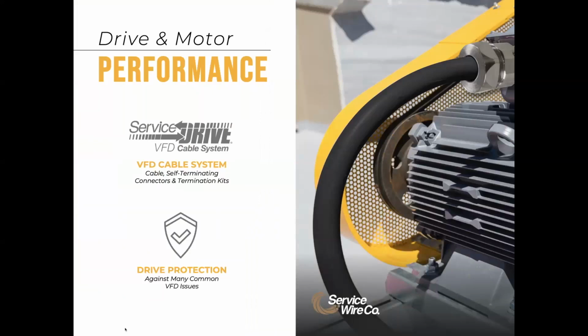VFD cables can be used in a wide range of processes inside of a steel mill. I've already mentioned their use in water, cooling, and filtering applications, but they can also be used in hot rolled steel processes, for example. Hot rolled steel production utilizes large rollers to move product. We've seen facilities with 200 plus rollers, with each roller having 10 horsepower motors powered by low voltage VFD. In this example, all of the cables were routed in covered cable tray to protect the cable from the heat.